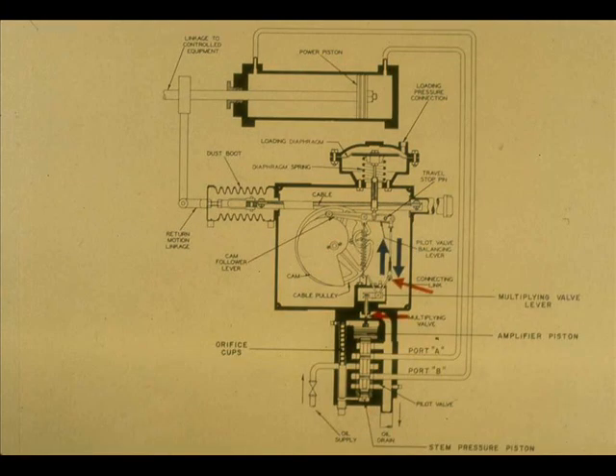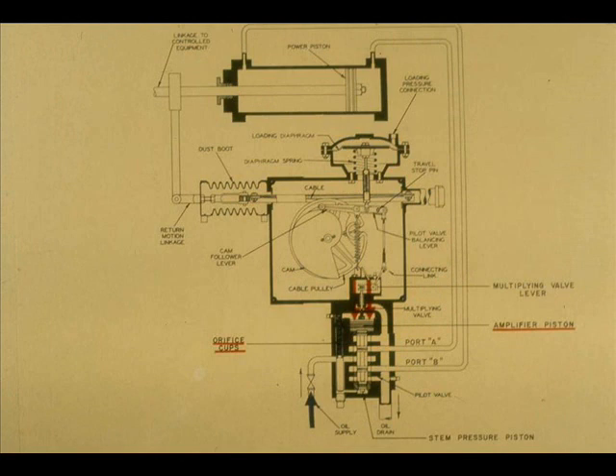As the connecting link raises and lowers, the multiplying valve operating lever raises and lowers the multiplying valve stem. A portion of the oil supply goes through the orifice cups. This is equivalent to the restriction orifice in a pneumatic relay. The reduced supply pressure acts upon the amplifier piston.